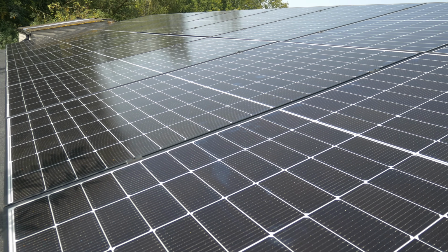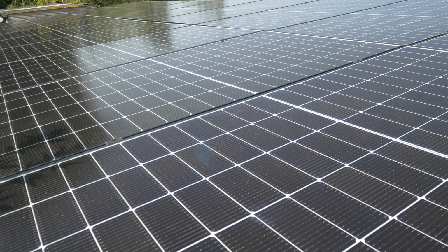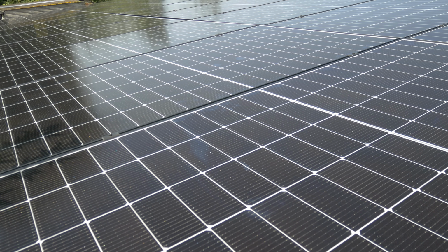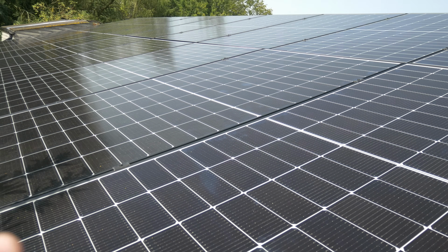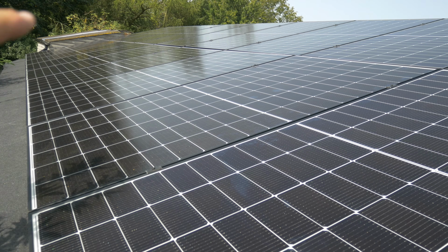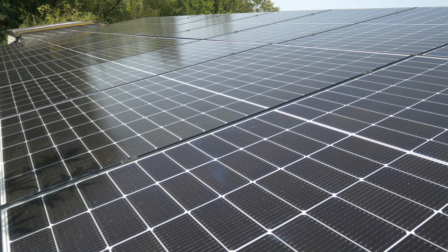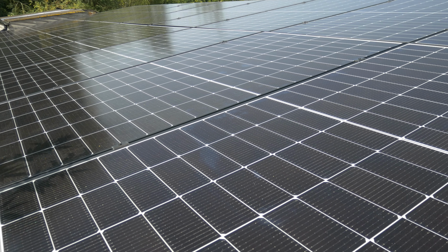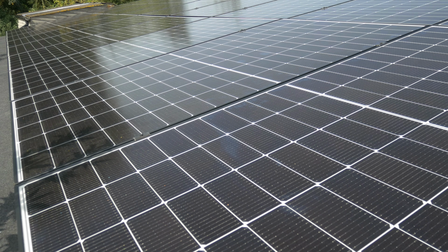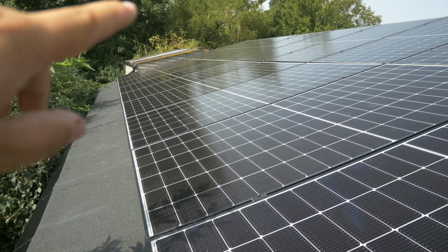It's at the perfect angle for the best generation through the year, and we're all up and running now, as you can see at the inverter, kicking out 3 kilowatts off this bottom string here. I still need to commission and test the top string, but it's a good indicator we're going to get some really nice generation. These are optimised because there's a tree over here, and as the sun moves across this back elevation, you can see at the minute it's high up in the sky.